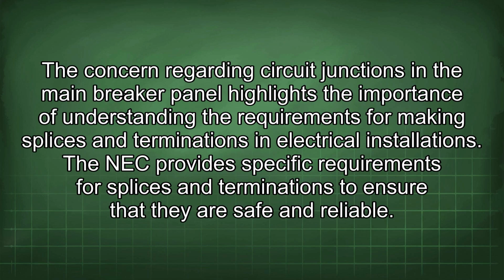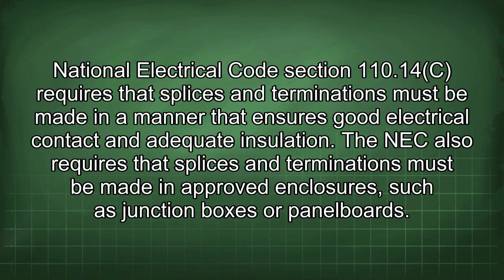The concern regarding circuit junctions in the main breaker panel highlights the importance of understanding the requirements for making splices and terminations in electrical installations. The NEC provides specific requirements for splices and terminations to ensure that they are safe and reliable. National Electrical Code Section 110.14(C) requires that splices and terminations must be made in a manner that ensures good electrical contact and adequate insulation. The NEC also requires that splices and terminations must be made in approved enclosures such as junction boxes or panelboards.